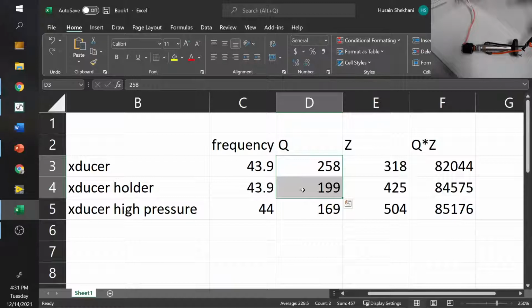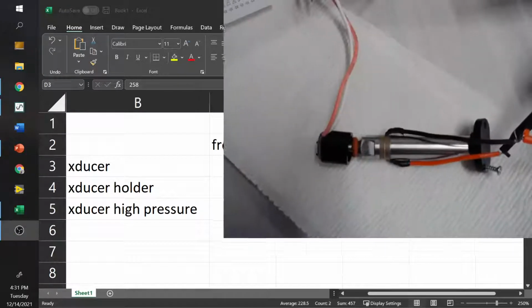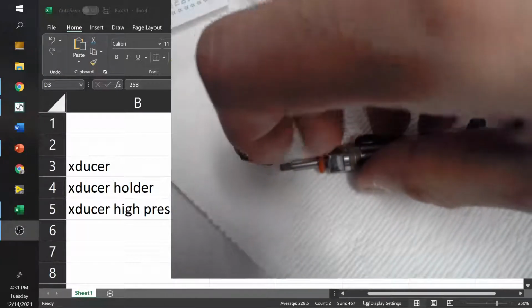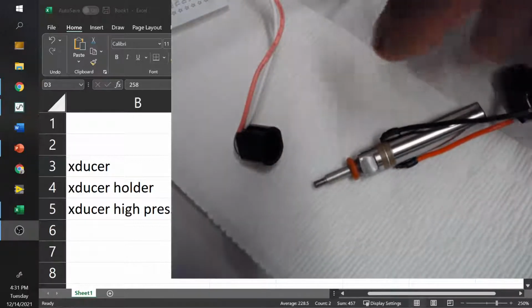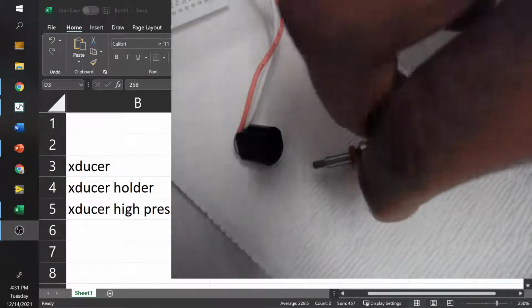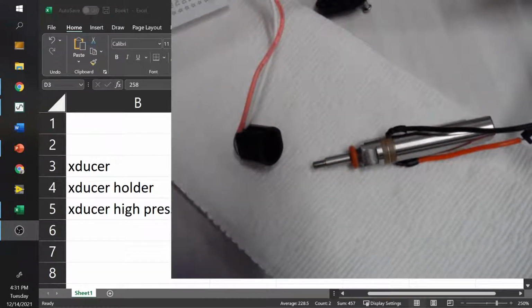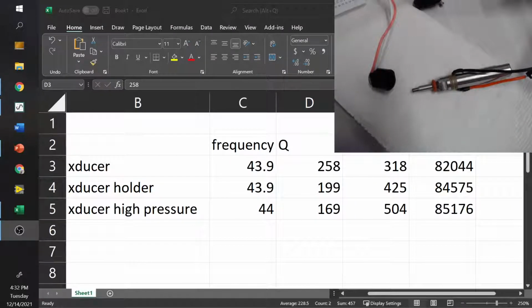The problem is that when you get to higher power levels, the oscillation of your device itself, let me just blow that up for you guys, is going to start rubbing against things and really causing even more losses due to higher power and higher oscillation levels. That significantly increases heat and damping in those areas. So you would be wise to test this under multiple conditions, both high power and low. But we do see that even in low power, we are reducing Q. So that's a concern there.